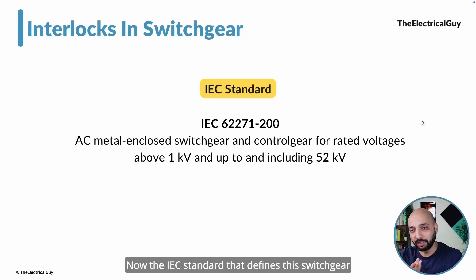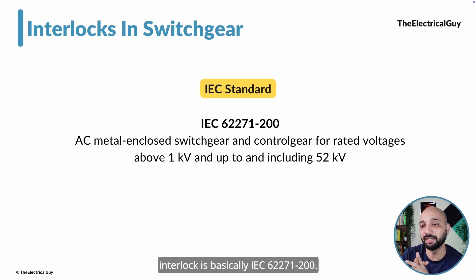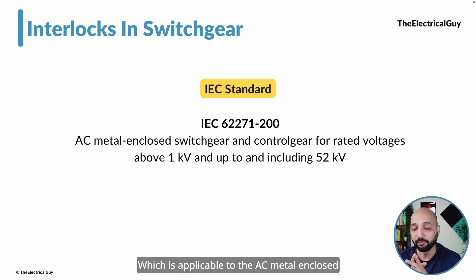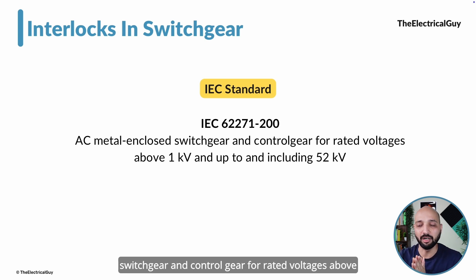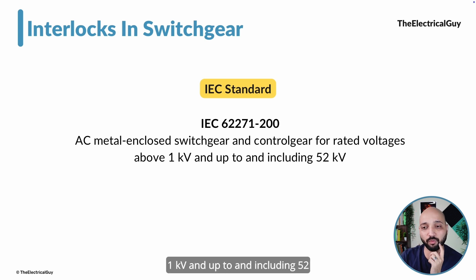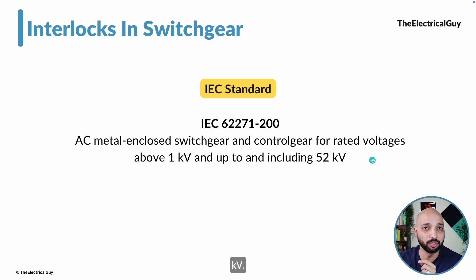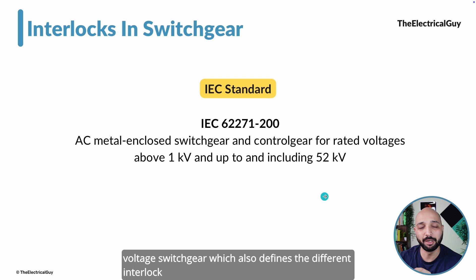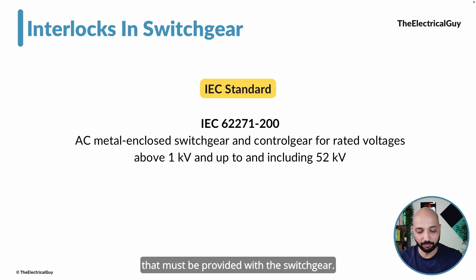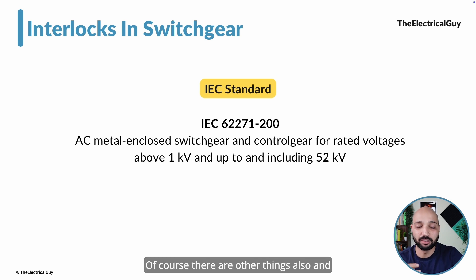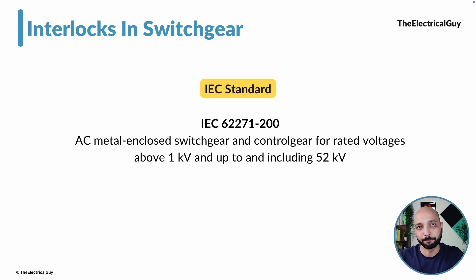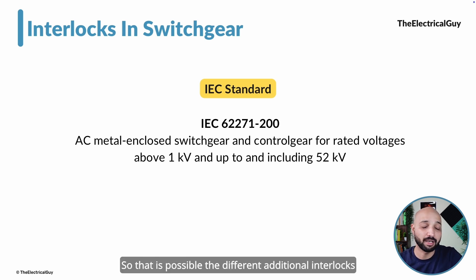The IEC standard that defines switchgear interlocks is IEC 62271-200, which is applicable to AC metal-enclosed switchgear and control gear for rated voltages above 1 kV and up to and including 52 kV. This is the parent standard for medium voltage switchgear, which also defines the different interlocks that must be provided. There can be additional interlocks beyond these two examples depending on the customer's requirements.